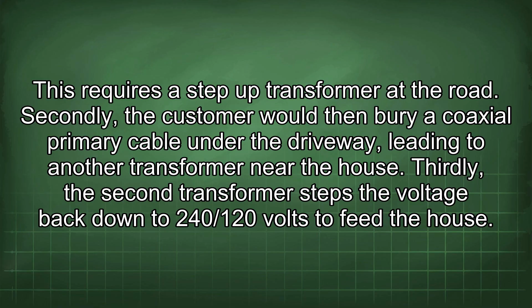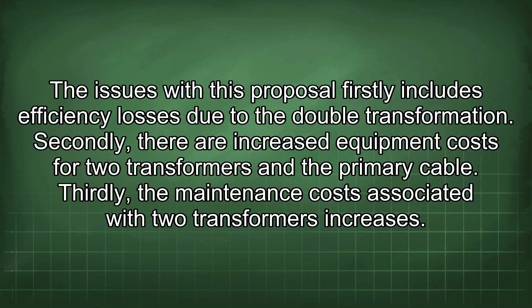The issues with this proposal firstly include efficiency losses due to the double transformation. Secondly, there are increased equipment costs for two transformers and the primary cable. Thirdly, the maintenance cost associated with two transformers increases. Fourthly, the complexity of the system increases the risk of failure. Fifthly, this setup may not meet electrical code requirements for residential services.